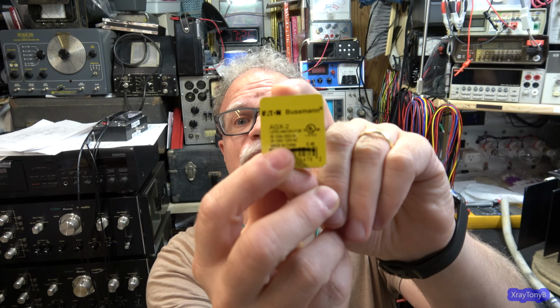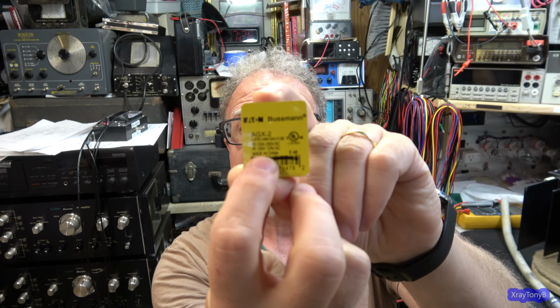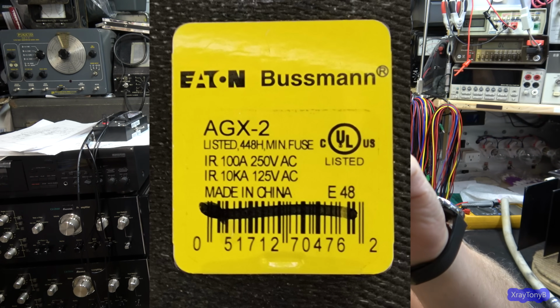But if you have a circuit that will exceed 100 amps, the same thing's going to happen to this as if you exceed its maximum voltage. It's going to take longer for it to blow. Now, if you have a lower voltage across there, like this, 125 volts, then it can actually break up to 10,000 amps. It's a huge difference just by cutting the maximum voltage in half.